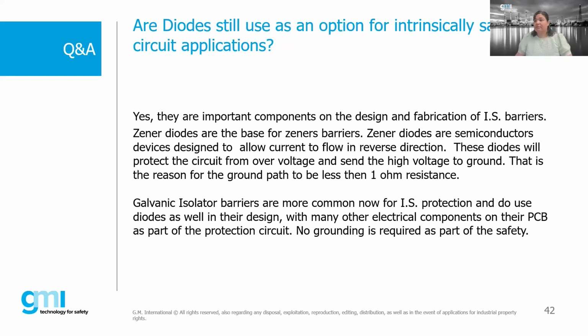Sometimes people build intrinsic safety into their boards at the board level. You could buy a PLC or other device that has intrinsic safety built in, likely with Zener diodes on the board itself, as opposed to using a separate intrinsically safe barrier from GMI or other manufacturers. So yes, they typically still use Zener diodes. In some cases they'll also use galvanic isolation, which isn't uncommon. It's very common for boards with an intrinsically safe output to have Zener diodes on the board and then a dedicated IS earth out of that panel.